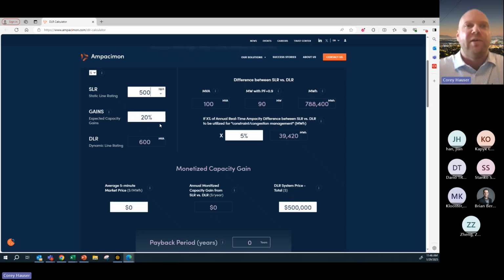We don't want to throw anything ridiculously unrealistic in this. So that is going to calculate, and since I'm so good at math and could have done this in my head, it will give you the 600 value. Obviously it's just 500 plus 20%, and we come to this 600 MVA. As we move over to the right here, we're going to look at the difference between the static line rating and the dynamic line rating. So we're going to take that 100 MVA gain and turn that into megawatts. We're going to do that by using a power factor of 0.9. So by doing that, we're taking this 100 times 0.9 and going from 100 MVA to 90 megawatts.